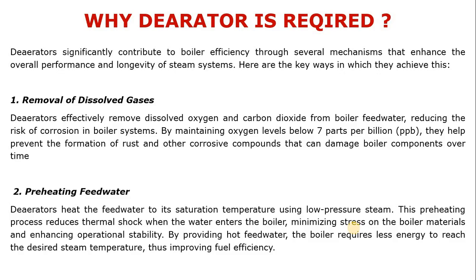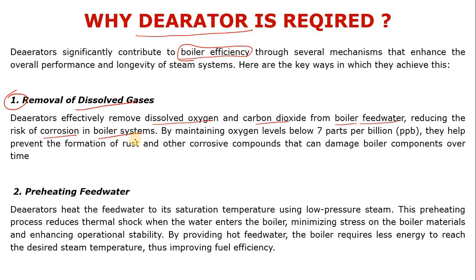Now, why is de-aeration required? The de-aerator is part of the boiler package and contributes to boiler efficiency. First, removal of dissolved gases: de-aerators effectively remove dissolved oxygen and carbon dioxide from the boiler feed water, reducing the risk of corrosion in the boiler system. By maintaining oxygen levels below 7 ppb, they help prevent the formation of rust and other corrosive compounds that can damage boiler components over time.